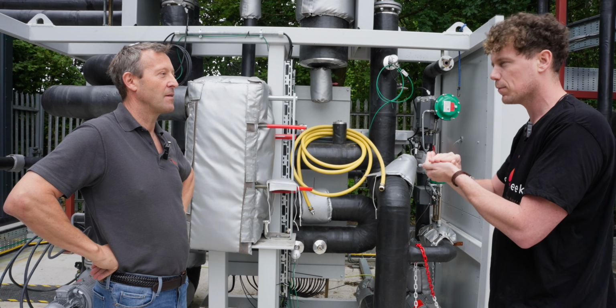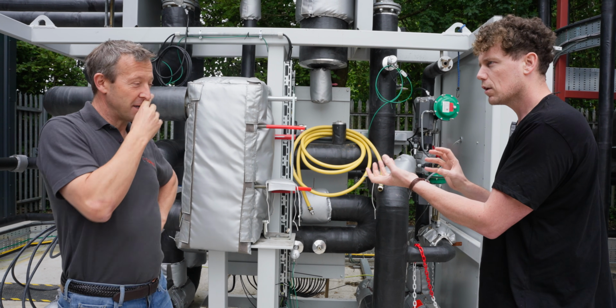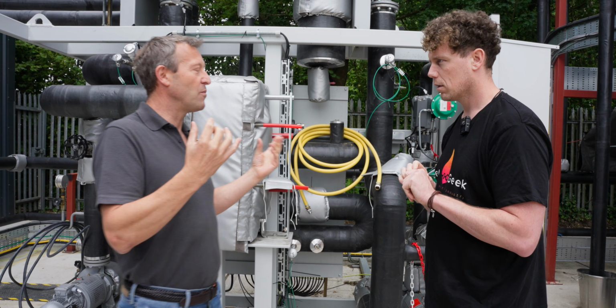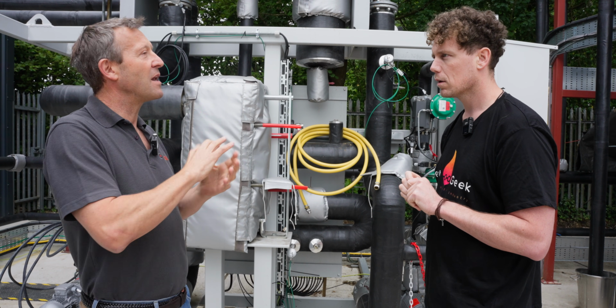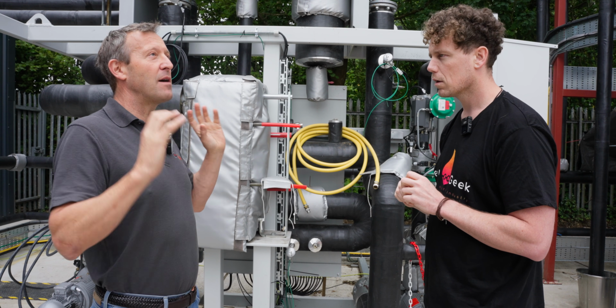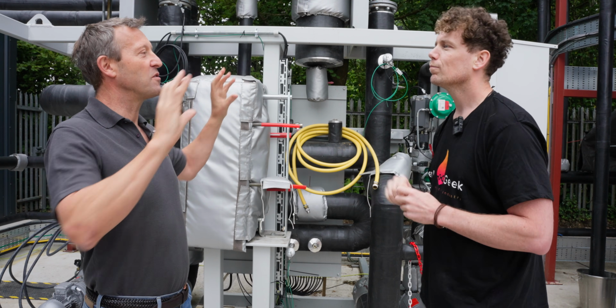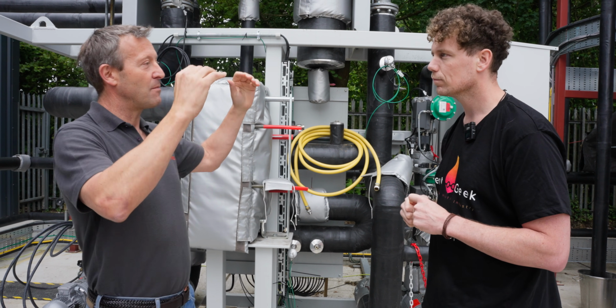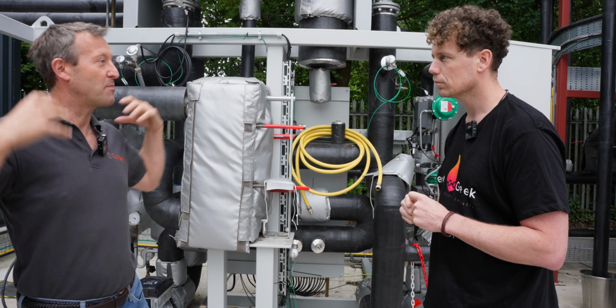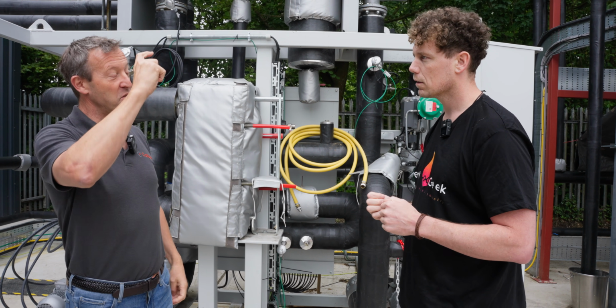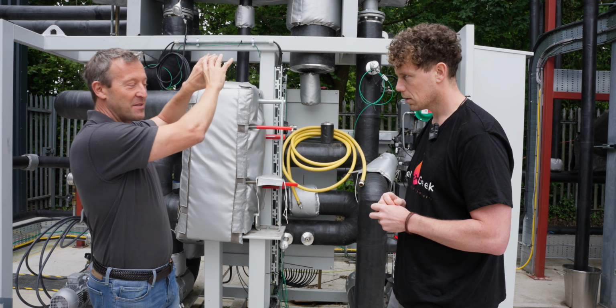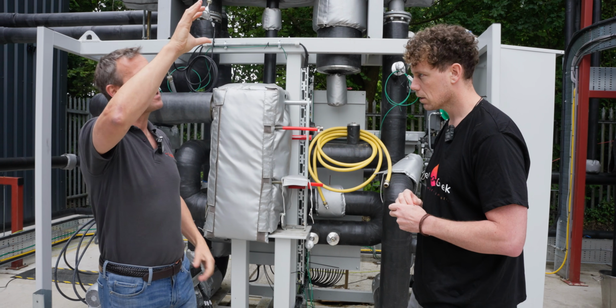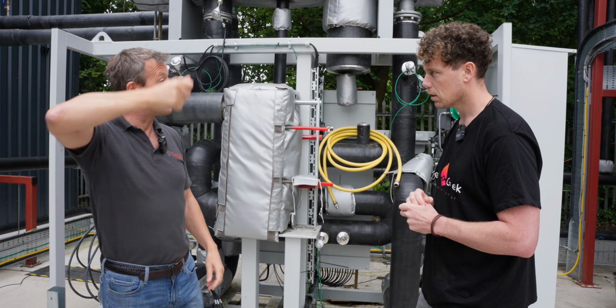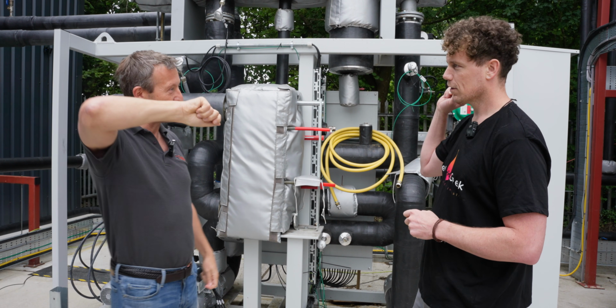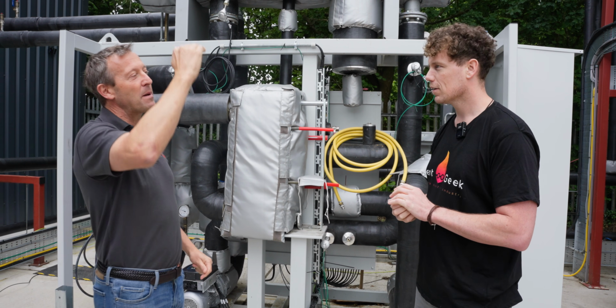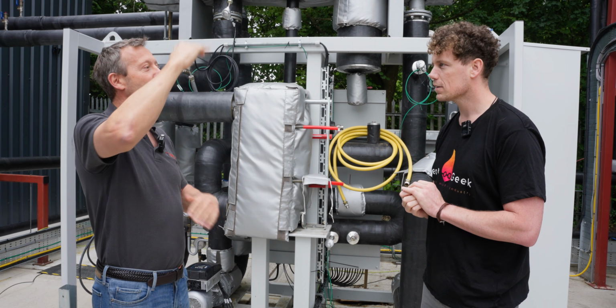We're keeping that in the system, so it just gets higher pressure. When you boil the water, the easy way to run it is there'll be a balance point. So if you want to run your steam network at, say, 10 bar, when people start to take steam off and cool it, the pressure drops. What everyone does is measure the pressure at the steam header, by the boilers, and aim for 10 bar. If it rises above, you turn the boilers down, and if it drops, you turn them up. So by measuring pressure, you're matching supply and demand.